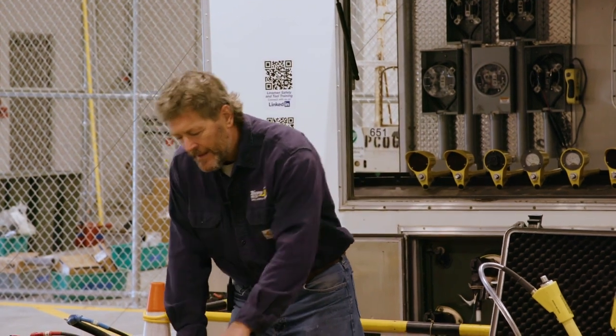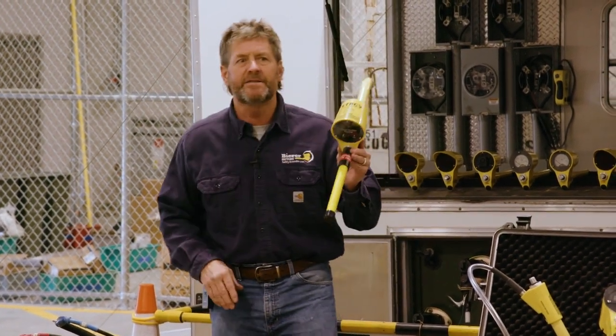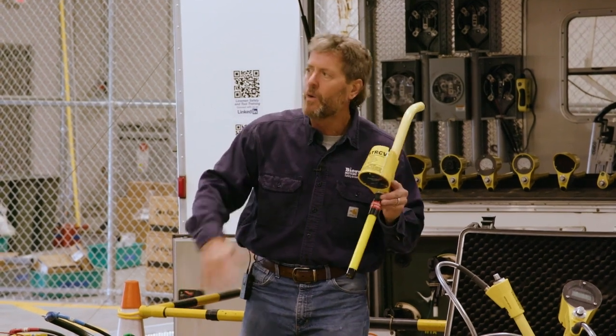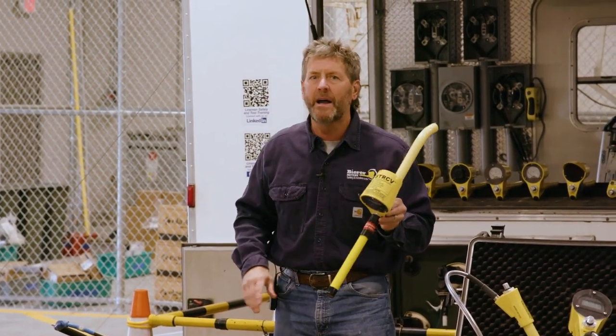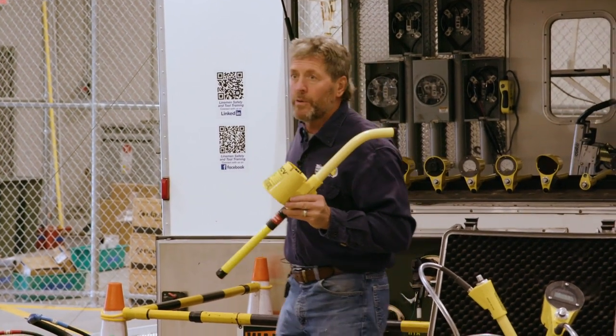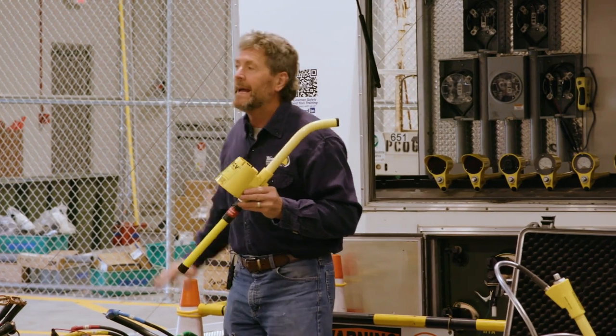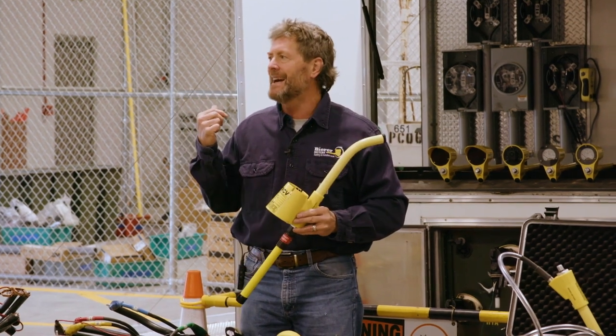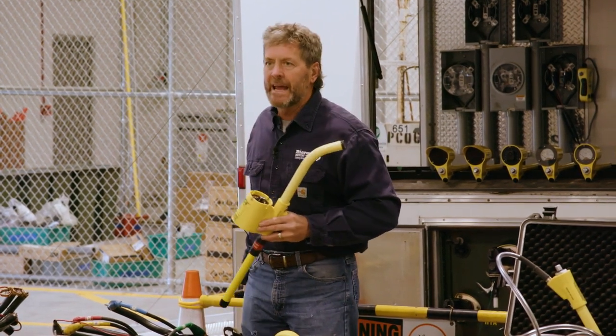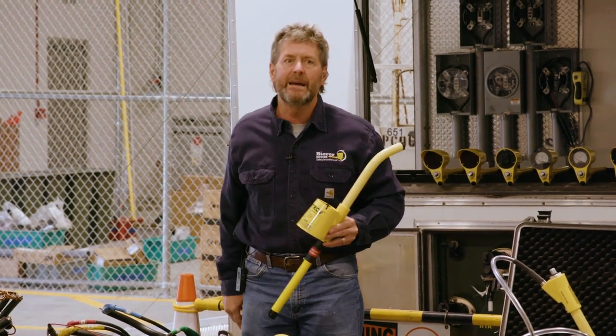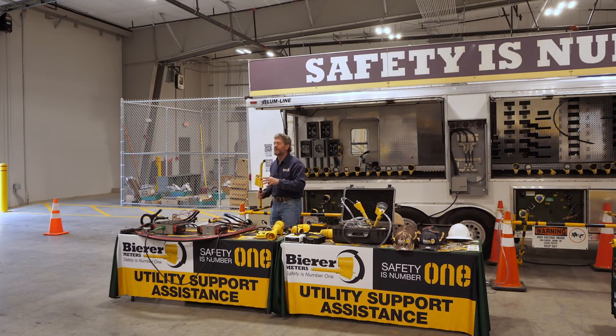Okay, that's the first function. The secondary function is we've got an STRCV, a service test receiver. This goes together with the kit or separately, but with this tool you can identify your secondaries at that pad mount. If you want to pull a particular customer off service so you can do some work and keep all the other customers on, this picks up the pulse, and now you can isolate that customer and re-tag those cables, since there are no tags or the label can't be read anymore. So now we can identify your secondaries. You can also use it to positively identify your feed in and feed out at the pad mount, and to ID your primary cable whether it's energized or de-energized.